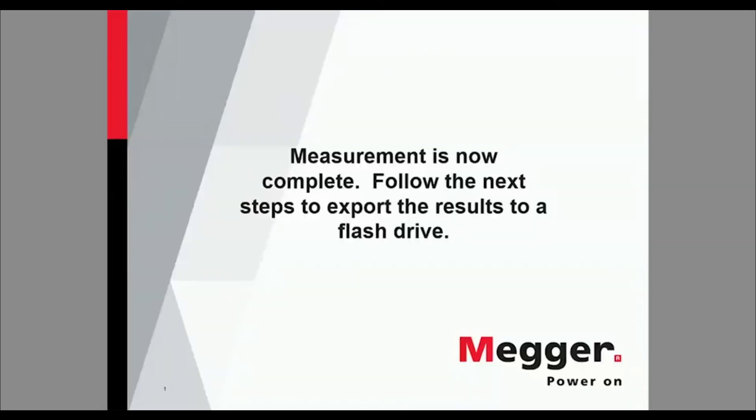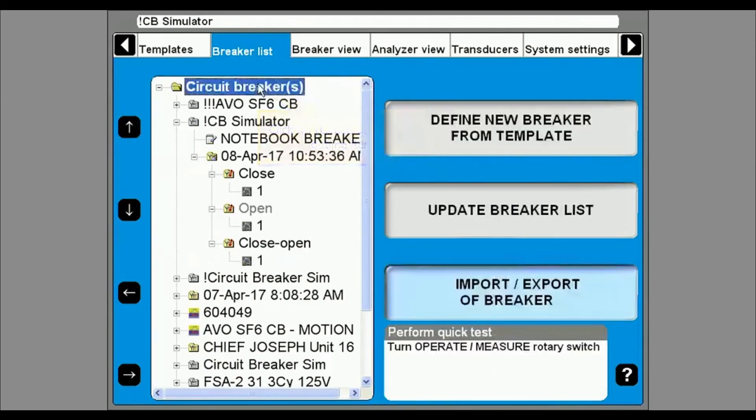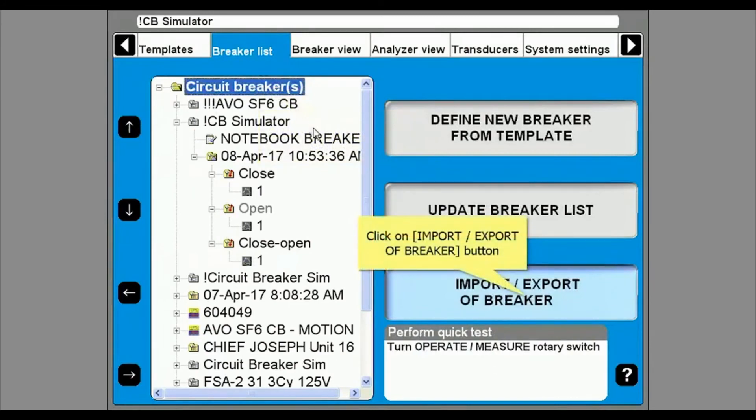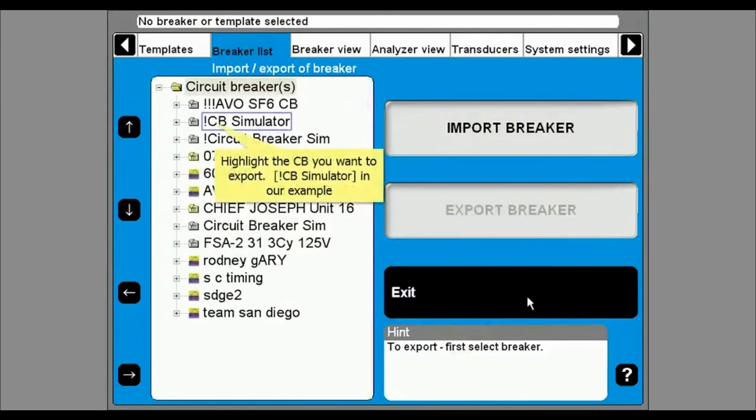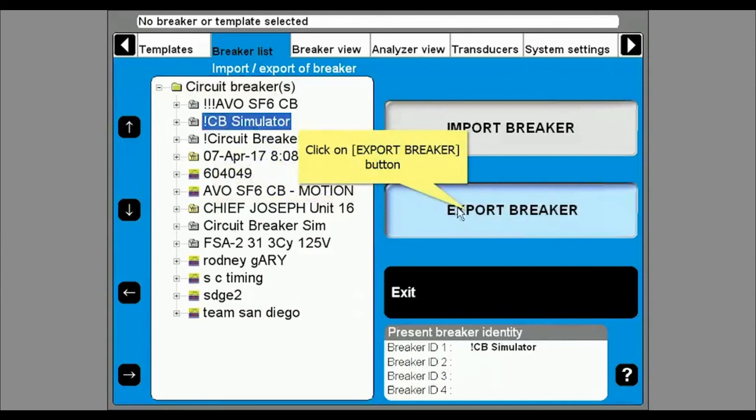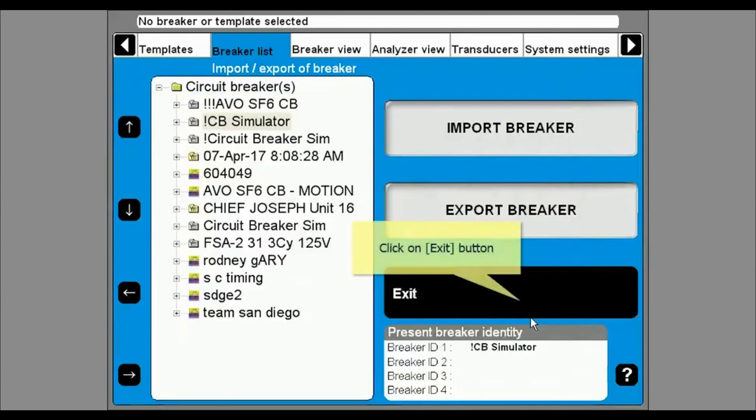The data is continuously saved to the unit but once the operation is complete you can save the information to a flash drive. Go back to the breaker list tab and highlight circuit breakers at the top. Click on the import/export of breaker button at the lower right and then highlight the breaker in the breaker list that you want to export. Click on export breaker and save the file to the appropriate location. Click on the exit button to finish saving.